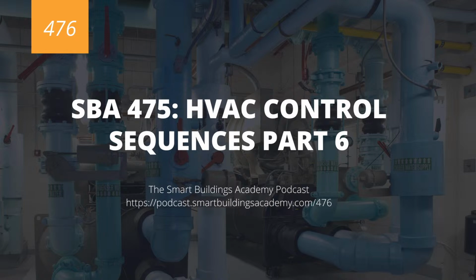Usually you'll have primary pumps with constant volume pumps, and you'll have the appropriate valves at the air handlers to handle a constant volume water stream. So just like hot water, there's various pumping setups, and you want to make sure that you're controlling based on how that works. But most of the time with air-cooled, you're only going to have primary pumps, and they're usually going to be constant volume.